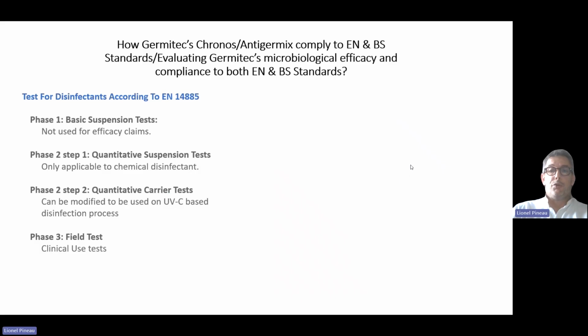Regarding EN tests, it is important to know that according to EN 14885, there are 4 types of tests. Phase 1 tests, which are basic suspension tests, not used for efficacy claims, just used to demonstrate the activity of active substances. Then we have phase 2 step 1 tests, which are quantitative suspension tests. But because they are suspension tests, they cannot be used for the UVC disinfection process, and they are only applicable to chemical disinfectants. Phase 2 step 2 tests are quantitative carrier tests, and these tests can be used on the UVC disinfection process. We will see later on how it's possible. And then we have phase 3 tests, called field tests or clinical use tests.